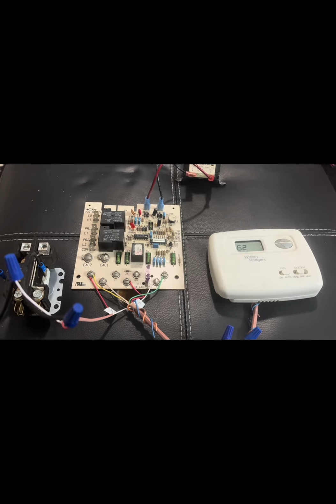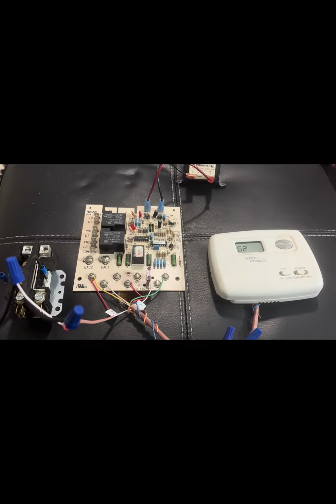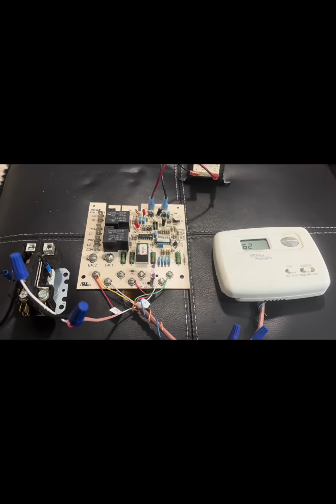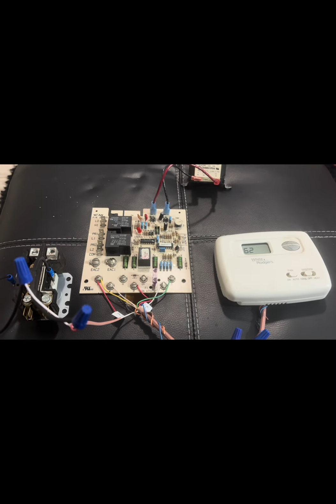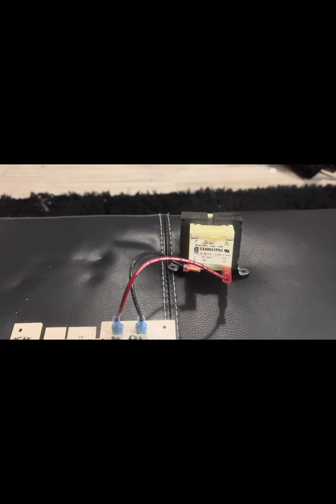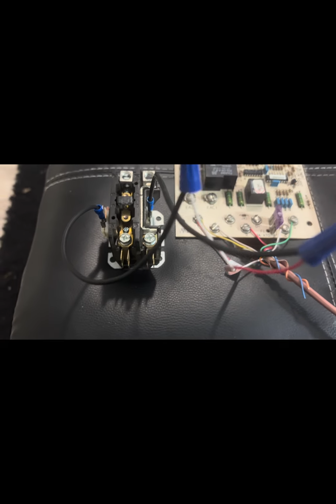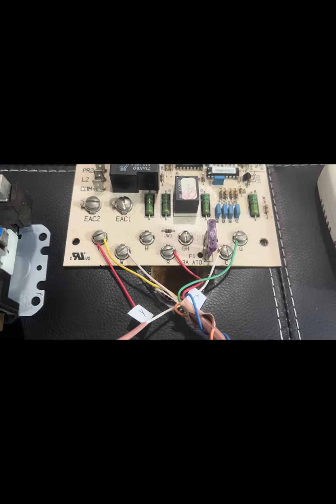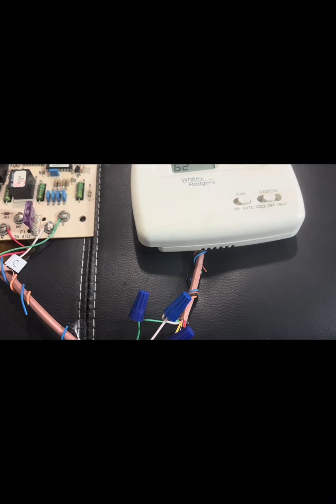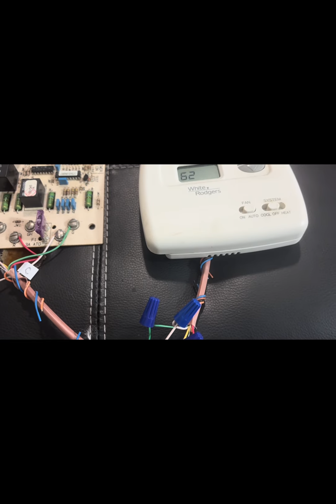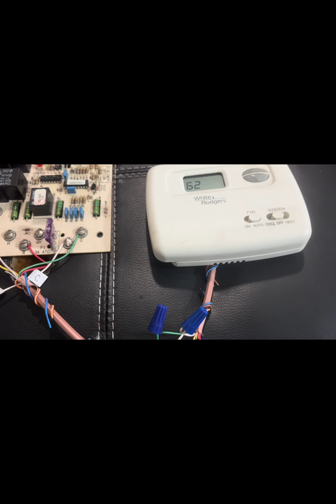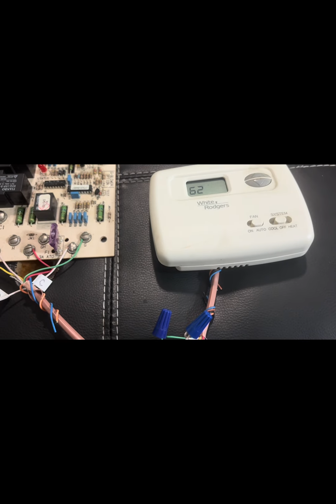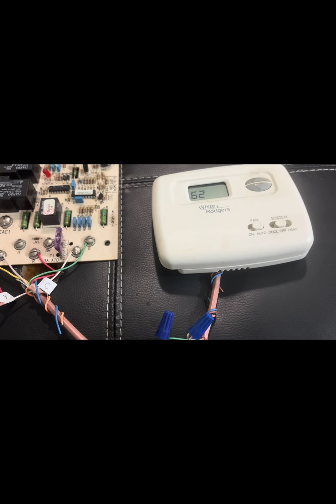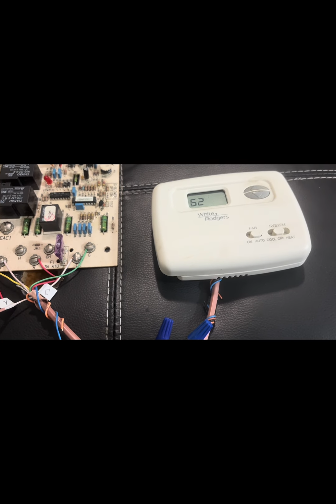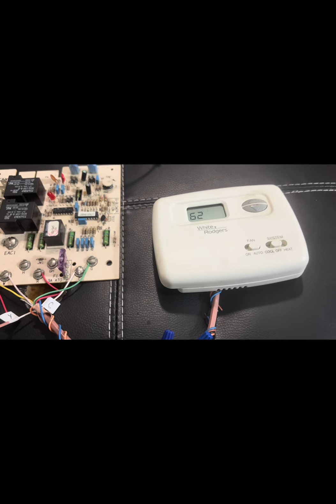So the 24 volt components, these are all components of the control circuit, not line voltage. So the 24 volt only components are your transformer, your thermostat, contactor coil, and the 24 volt terminals on your control board. Now we know the thermostat sends 24 volt signals to tell the system what to do. Common terminals used on a straight cool system will be your R for 24 volt power, C for common, Y for compressor, G for blower, and W for heat.